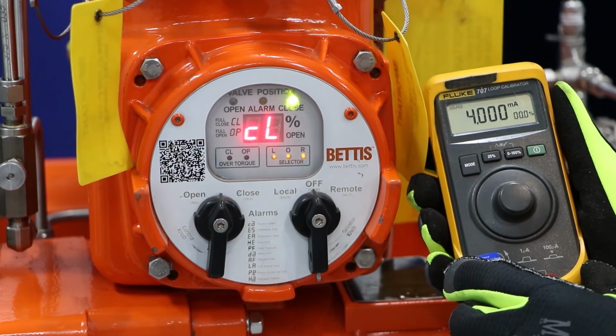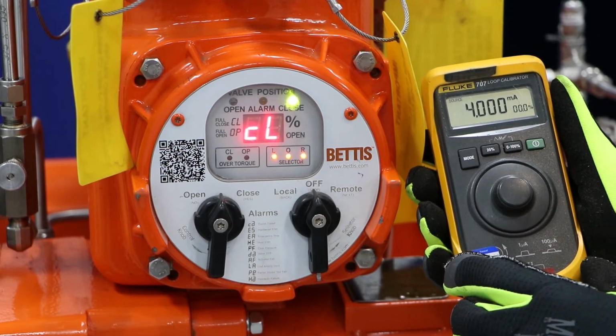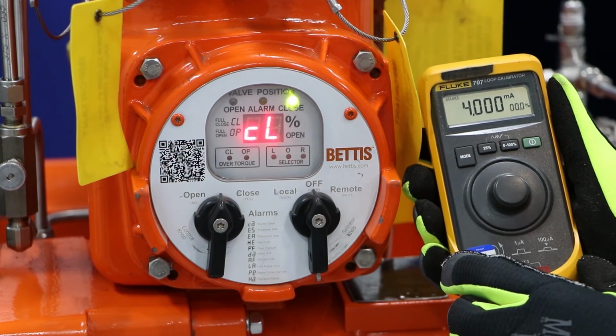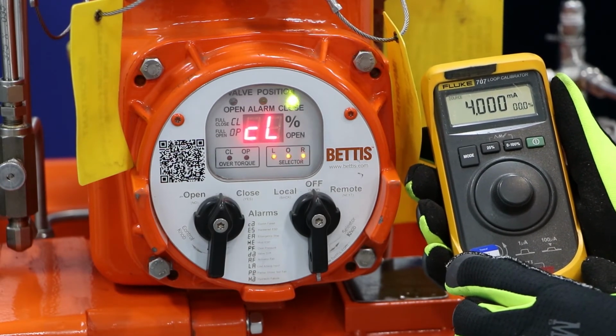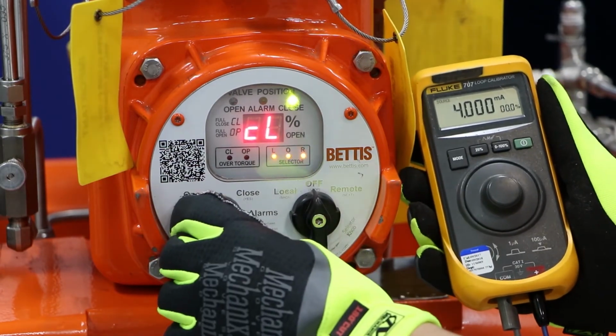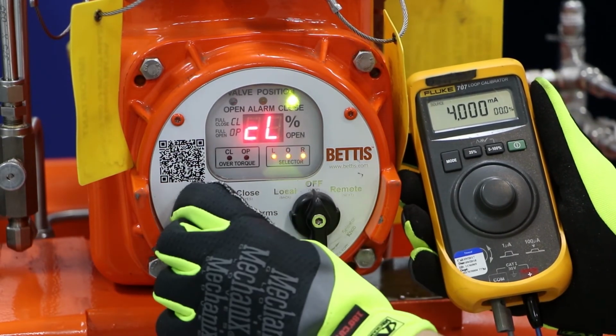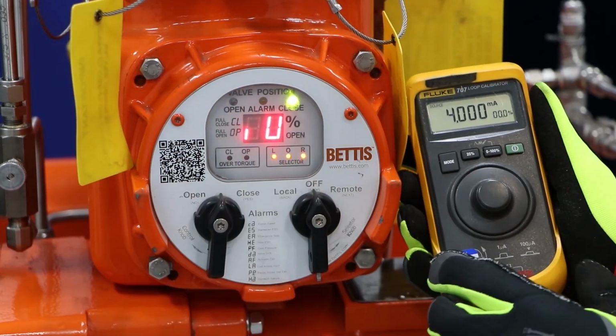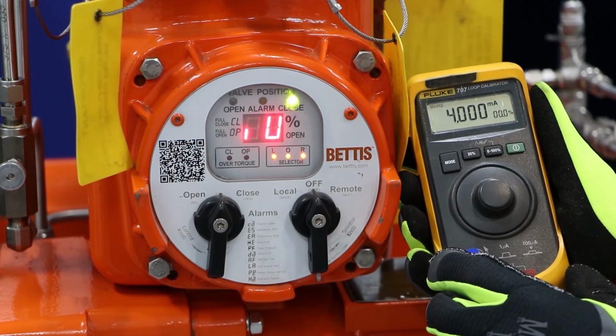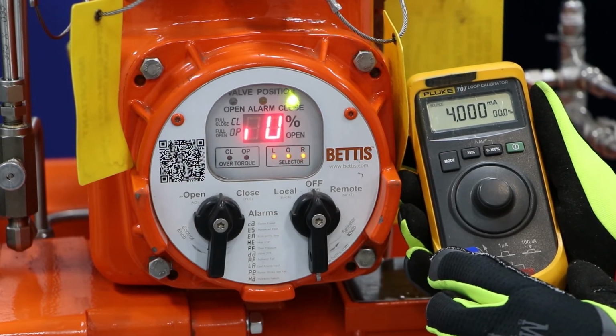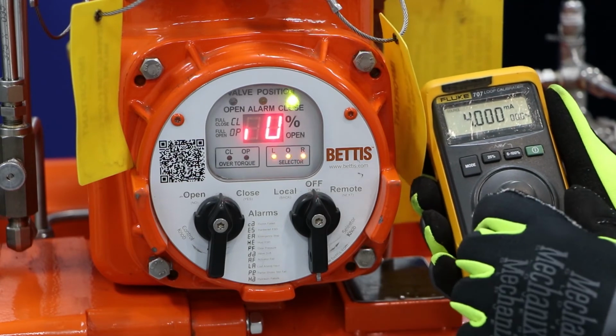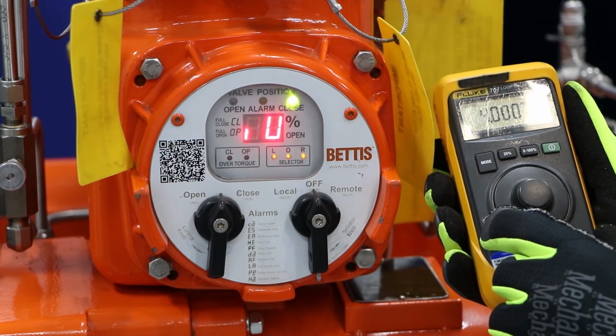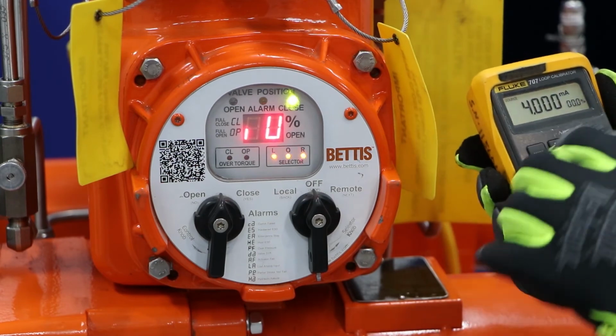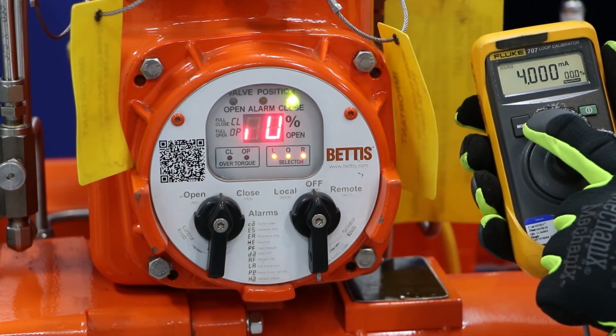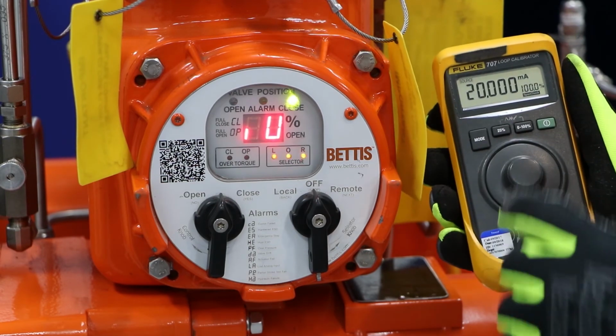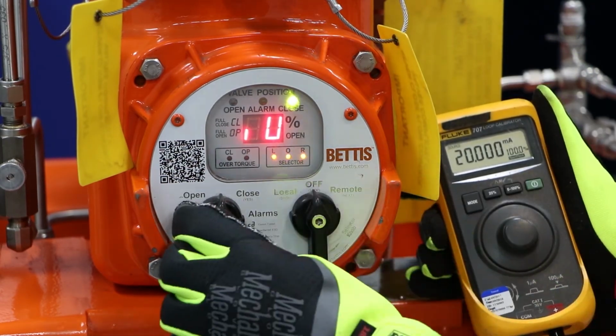And you're either going to see CL or CF. If it says CL, that means your lower limit has been set. If you see CF, that means your lower limit failed, and please try again. Now in this case, we've passed the lower limit, and it has been set, so we're going to hit yes. Next, you'll see IU. IU is your upper limit for input calibration. In order to set your upper limit, you want to go and set your analog current source to 20 milliamps. So we'll go ahead and set this to 20. There we go. Once you set to 20 milliamps, you hit yes.